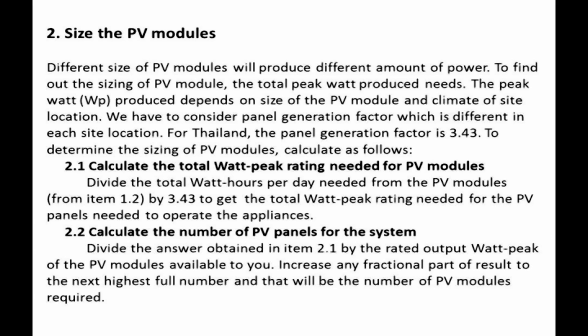Step 2.2: Calculate the number of PV panels for the system. Divide the answer obtained in Step 2.1 by the rated output watt-peak of the PV modules available to you. Increase any fractional part of the result to the next highest whole number — that will be the number of PV modules required.